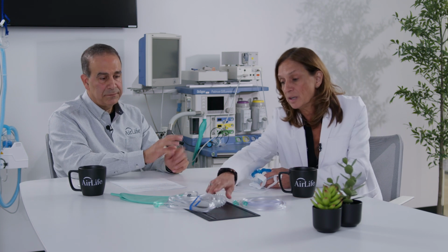Okay, so the SuperNO2VA is a nasal CPAP that has been around for quite some time, because patients with obstructive sleep apnea are treated with nasal CPAP taken home with the machine. What this SuperNO2VA does now is allow us to use it without a CPAP machine, and it's one unit that actually seals, and here's an example of it, around the nose so that it will cause positive pressure using 10 to 15 liters per minute flow, either using your anesthesia machine circuit, or what they have come up with, the Jackson-Reese with the pop-off valve as well, that you can use for transport with the patient.